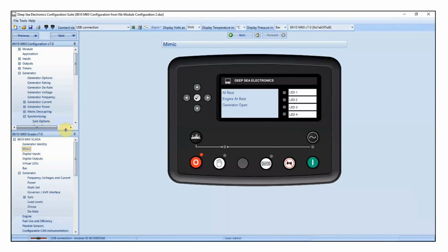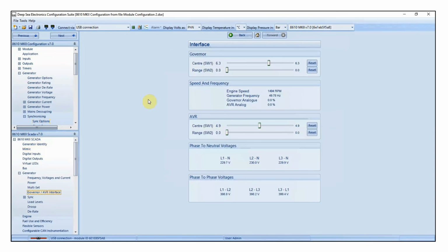Now, one thing we do get asked quite a bit is, when I tick that box, what actually should happen with switch 1? You'll see with the video, even though I've ticked the box output reversed, as I increase the switch 1 value, the frequency still decreases, and that is correct. That tick box for output reversed only affects switch 2. It has no effect on switch 1.